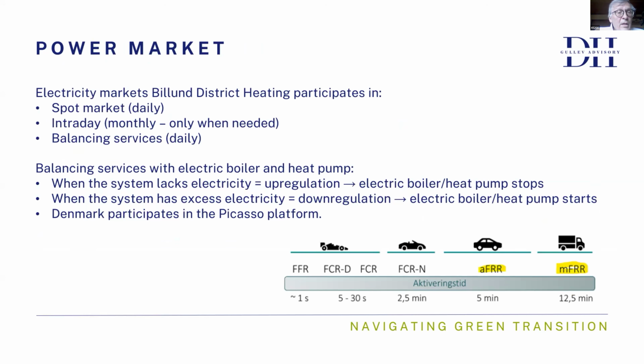So when we talk about the power market, Billund District Heating participates in the spot market on a daily basis. They participate in intraday and monthly markets only when needed, and in the balancing services daily. The balancing service is where they make good business operating the e-boiler, but it's also possible to operate the heat pump on that market, as long as you have storage facilities for the heat, so you disconnect the connection between heat production and actual heat demand.